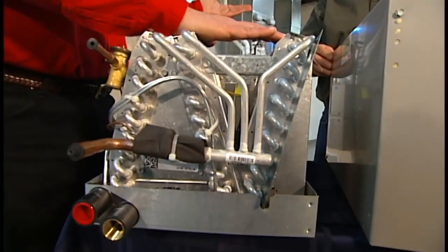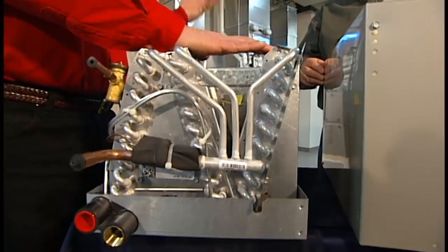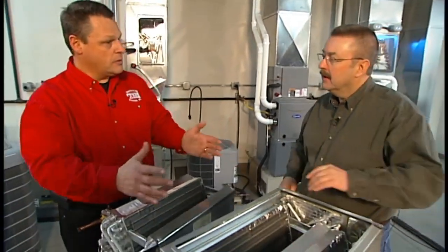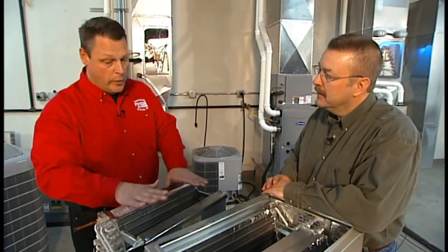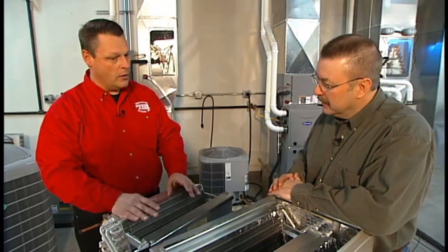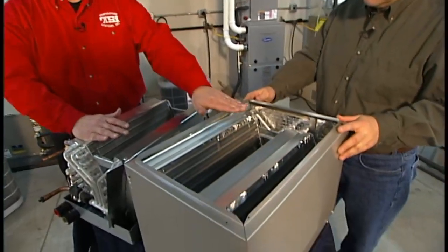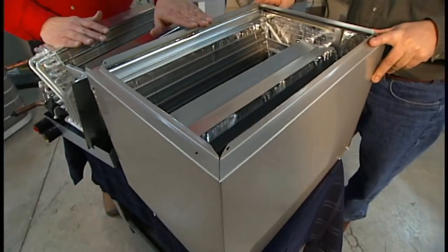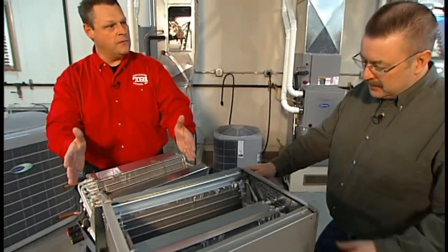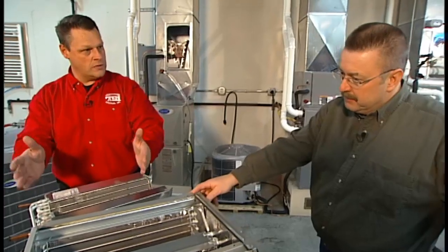In an existing furnace, we may be coming into somebody else's brand. It doesn't necessarily fit as a cased model, so what we would do is come in with an uncased one, customize the plenum around it, and you're good to go. Whereas if we're replacing a furnace and air conditioner, in most cases they'll come in with a cased coil that physically matches the fit and finish and size of the furnace it's going to be sitting on.